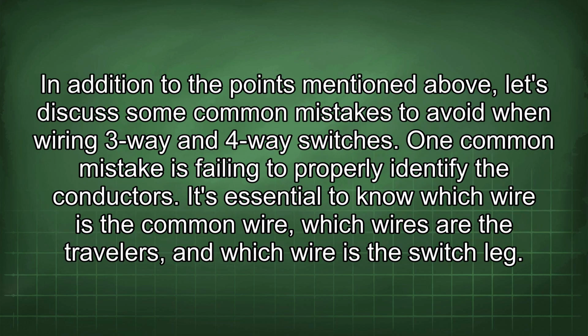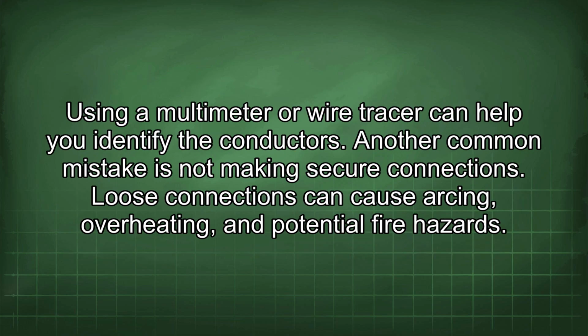In addition to the points mentioned above, let's discuss some common mistakes to avoid when wiring 3-way and 4-way switches. One common mistake is failing to properly identify the conductors. It's essential to know which wire is the common wire, which wires are the travelers, and which wire is the switch leg. Using a multimeter or wire tracer can help you identify the conductors.